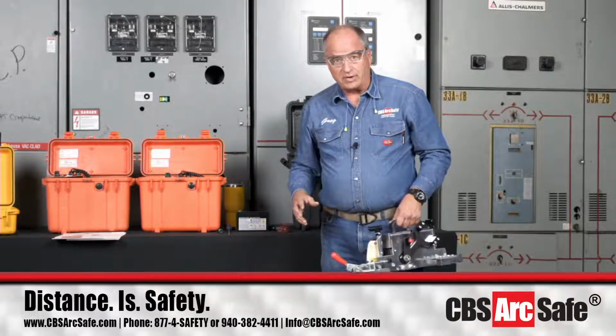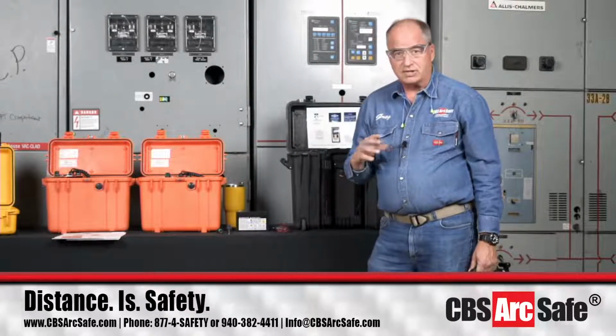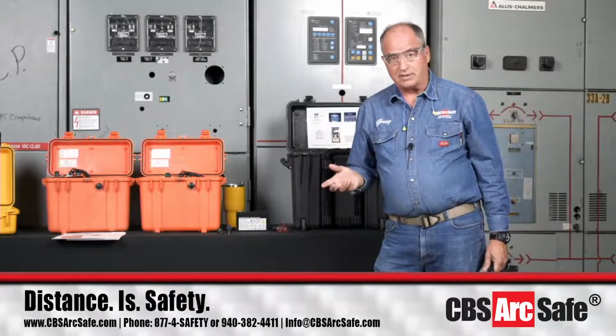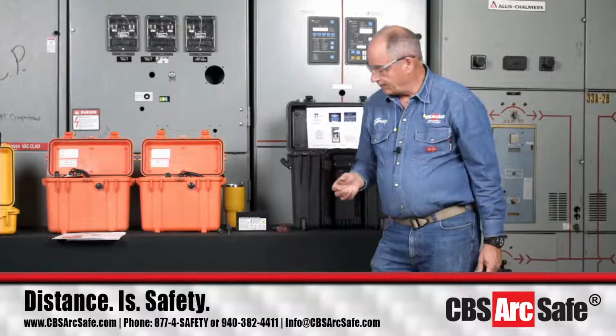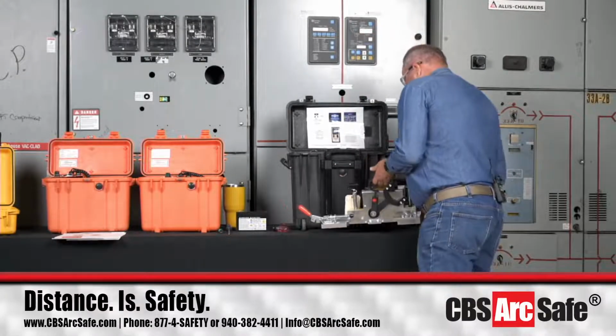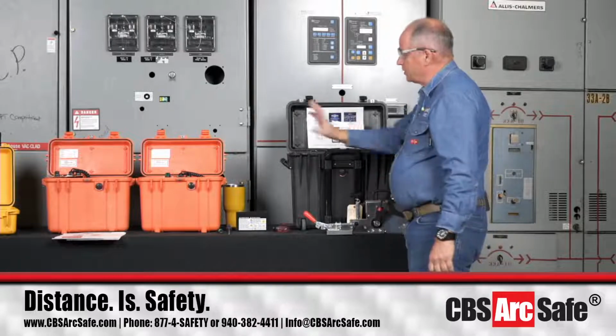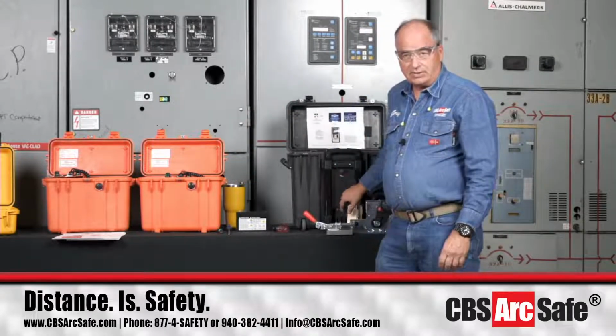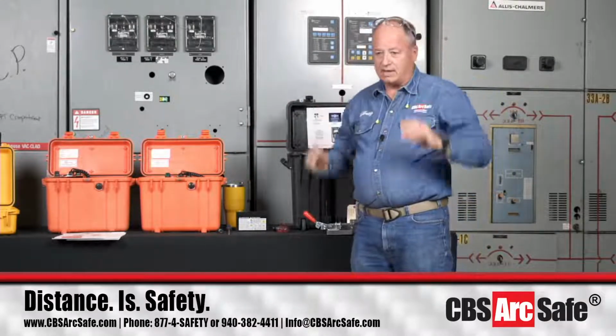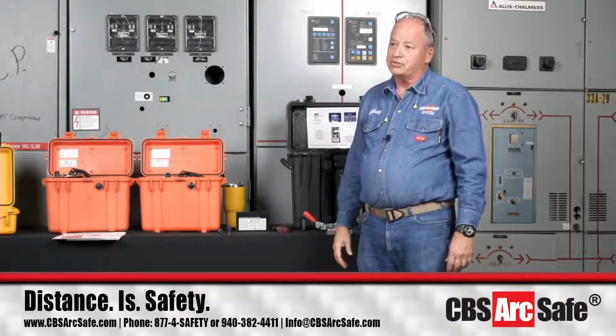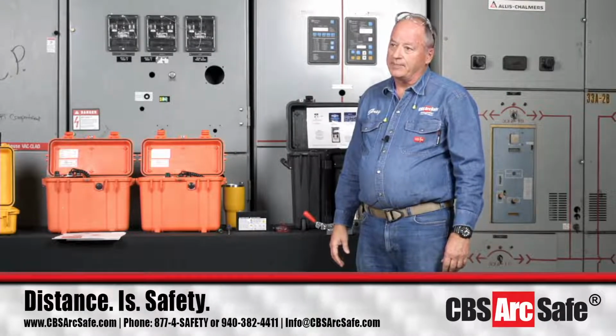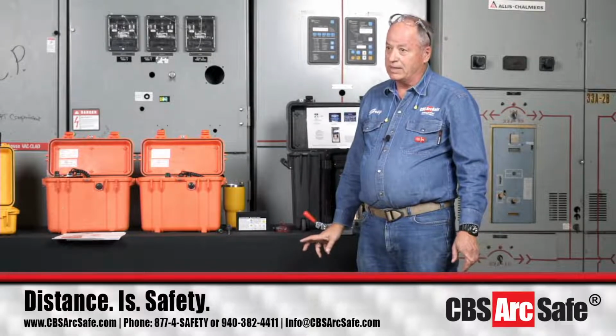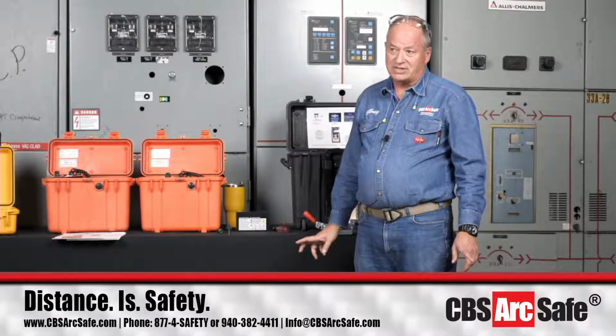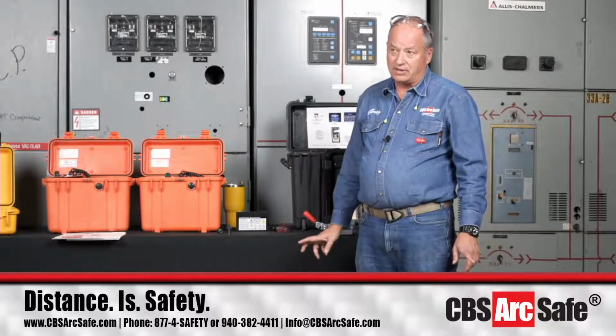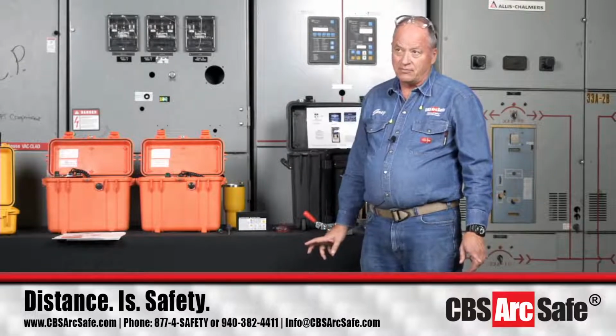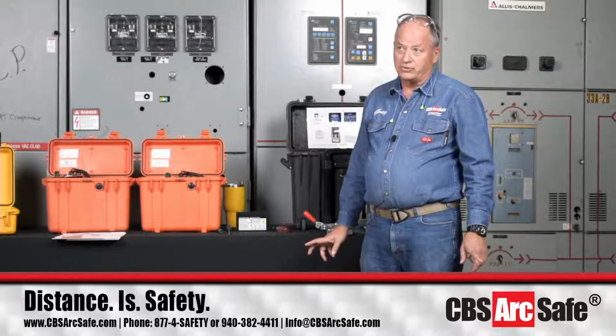What we normally recommend is that people exercise the RSO before putting it on the equipment and using it. If you have a fresh set of batteries in an RSO, we actually had 2 different switchgear manufacturers have us do testing, and we got over 1,000 cycles on an RSO for one full charge.